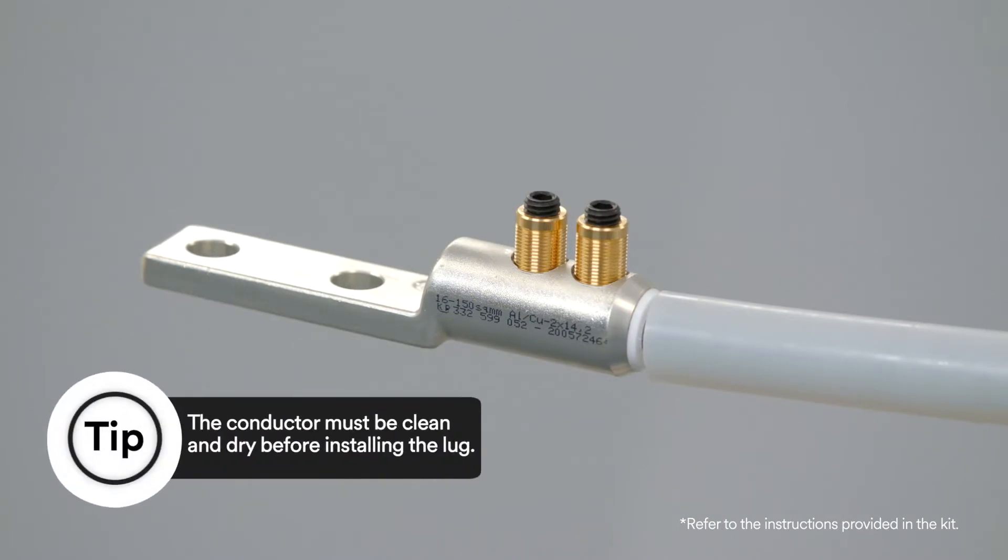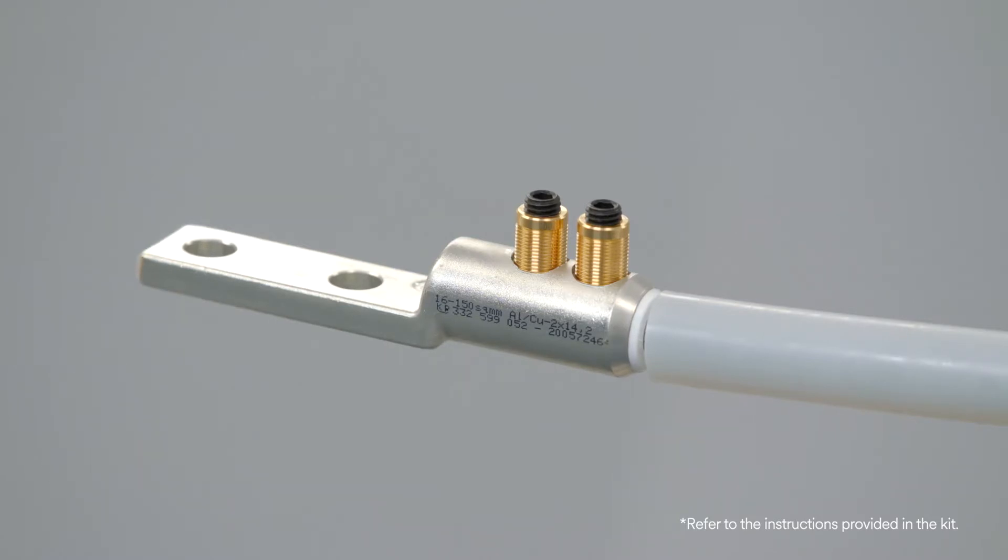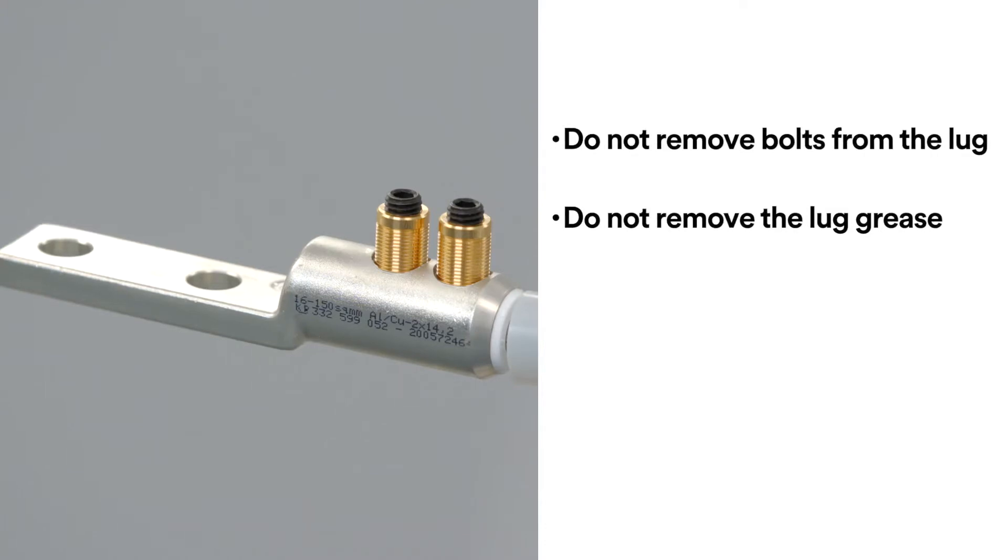For this video, we will be using the 3M Mechanical Shear Bolt 2-hole lug QL2 series. When installing the lug, there are a few things you must remember. First, do not remove bolts from the lug and do not remove the lug grease as it is pre-greased for the installation.